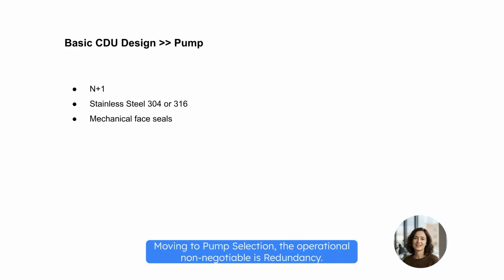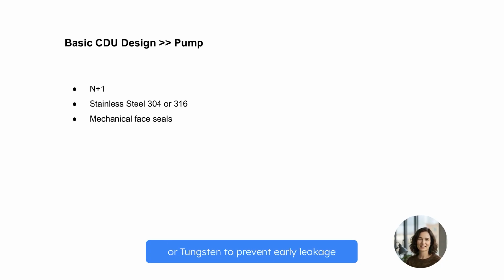Moving to pump selection, the operational non-negotiable is redundancy. You must design for at least N+1. This ensures continuous flow even during a pump failure or scheduled maintenance. For construction, standard stainless steel 304 or 316 is required, but pay special attention to the mechanical face seals. Specify high-wear materials like silicon carbide or tungsten to prevent early leakage.